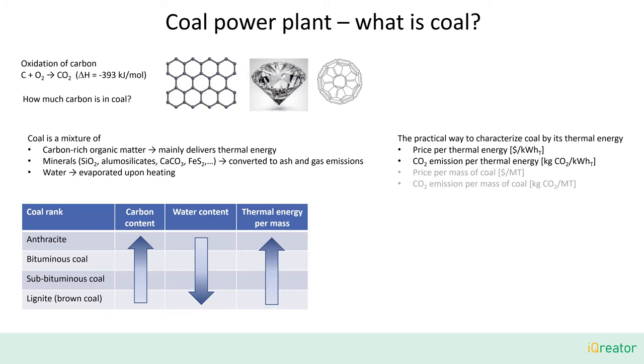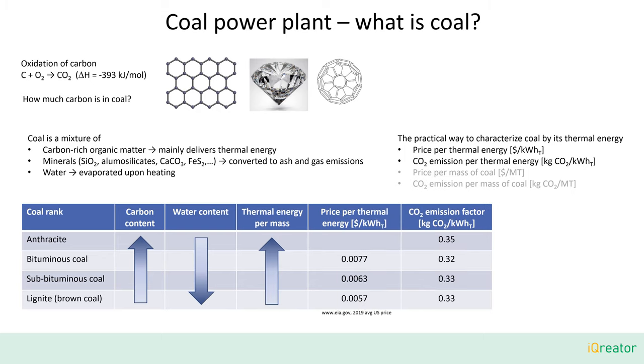There are different grades of coal. The higher the grade, the higher also the carbon content and consequently also the thermal energy per mass. For coal power plants, the lower ranks, bituminous coal or also called hard coal, and lignite are the most common. Prices are way less than one cent per kilowatt hour thermal. They have all similar CO2 emissions, around 0.33 kilograms per one kilowatt hour thermal. One should mention that lignite can be really rough, sometimes just containing 20% of carbon. So for lignite, the shipping costs are in general very high, which leads to the fact that lignite power plants are usually in very close proximity to the lignite mine. In contrast, hard coal can be easily transported economically by ship or train all over the world, which allows coal power plants to be built almost anywhere.